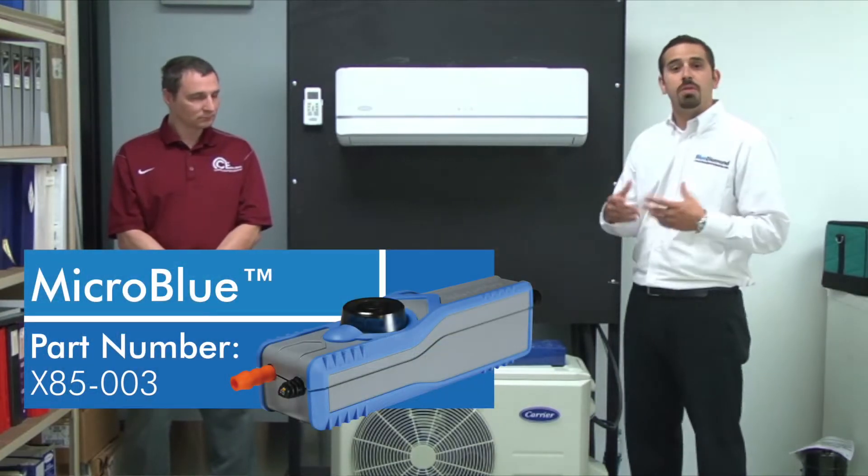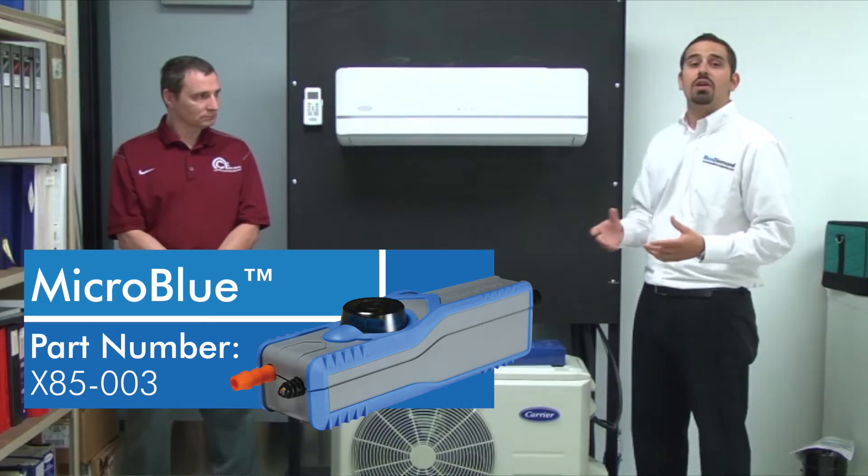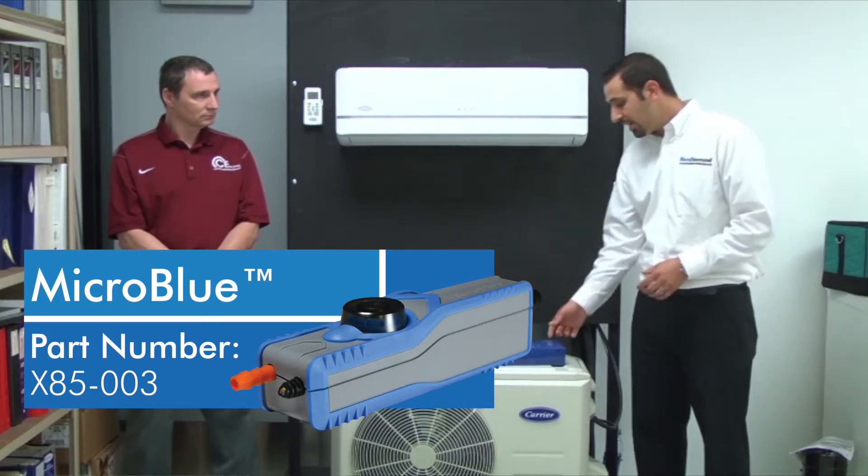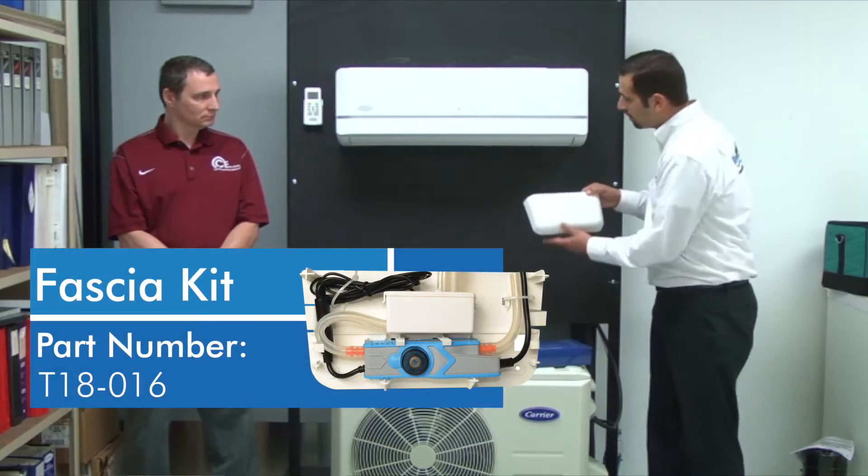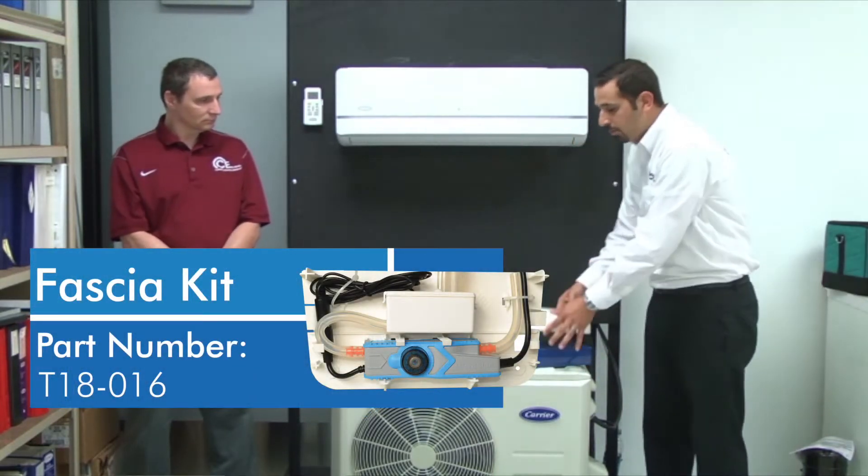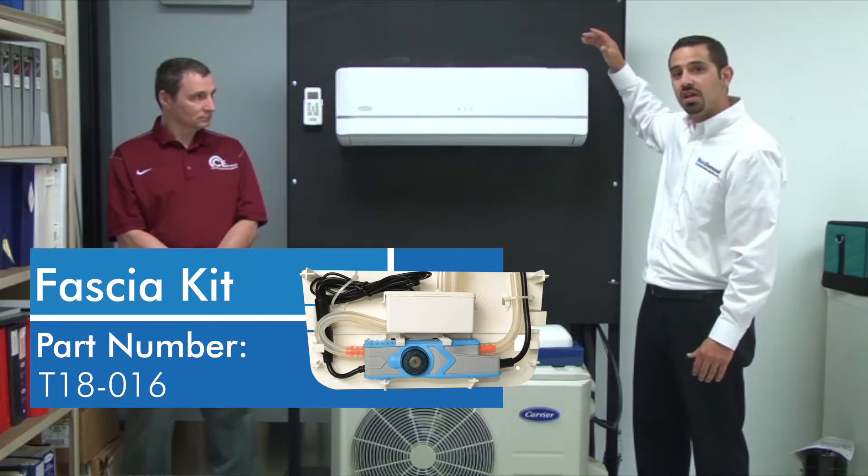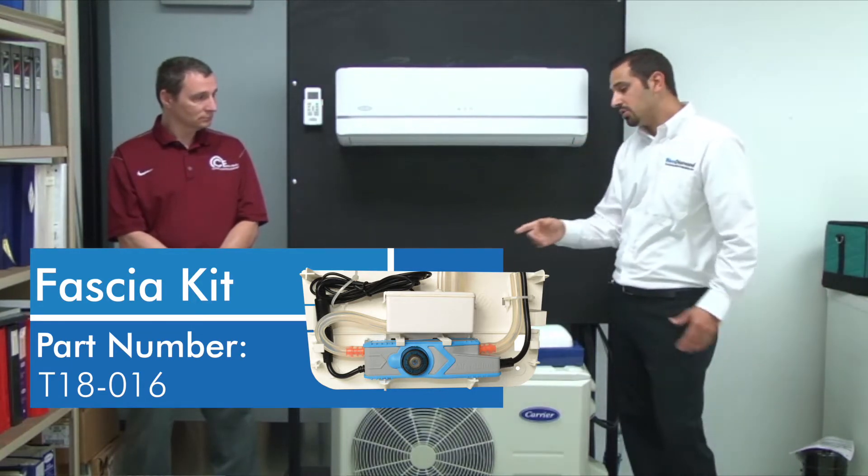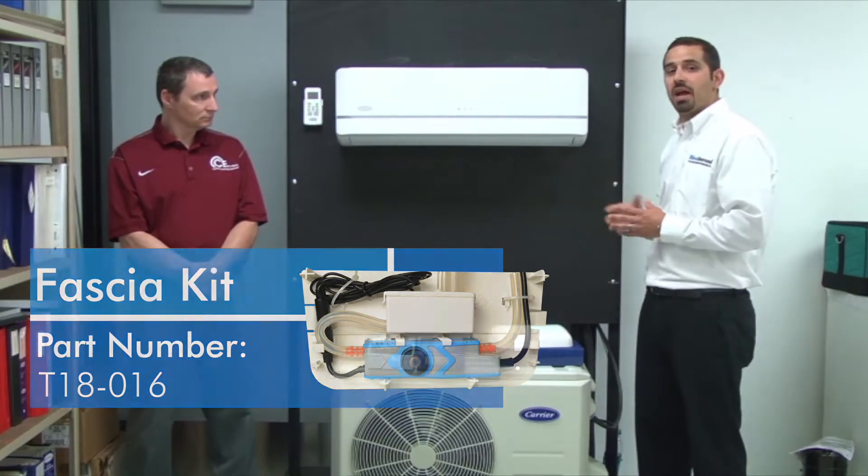It creates suction, it's positive displacement, so you can actually mount it in a variety of options. We have an undermount application that we can provide the plastic cover for and the pump can be mounted underneath. But the pumps also create suction so they can be mounted above the unit in any orientation, and you'll also notice the Micro Blue is small enough to mount in the back of the unit.